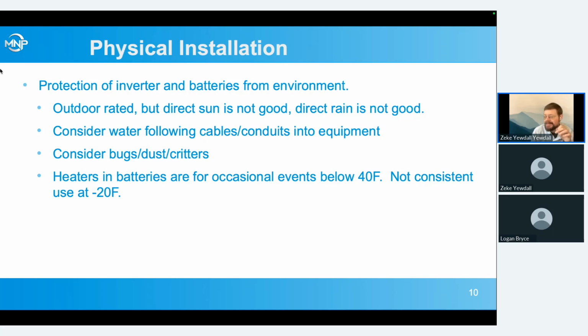So in some cases, it would be better to keep that battery warmer so it's ready to accept a charge sooner the next morning, rather than often wasting a lot of solar power the next morning because you're just putting a little bit into the heater rather than full power into something. But if you turn it on overnight to keep it warm, you risk draining the battery for no reason if maybe it's still snowy the next day and the sun didn't come out, and you just keep draining that battery. So we are actually playing around with some different firmwares and revising some of that, possibly even making it selectable which option you want for behavior of the heaters, whether you want them to be more aggressive in preheating the battery to keep it from dropping down, or never draw from the battery and only draw from incoming charging. That is something we're actually working on some improvements on.